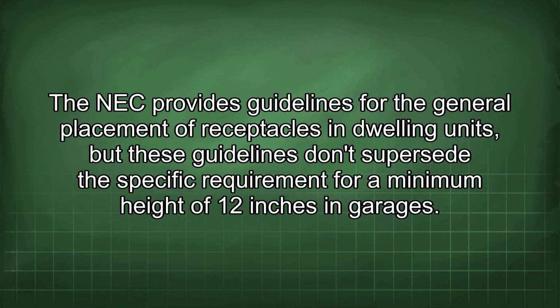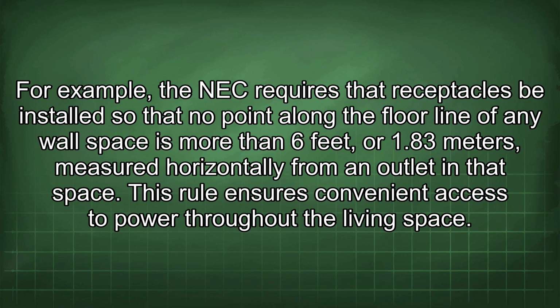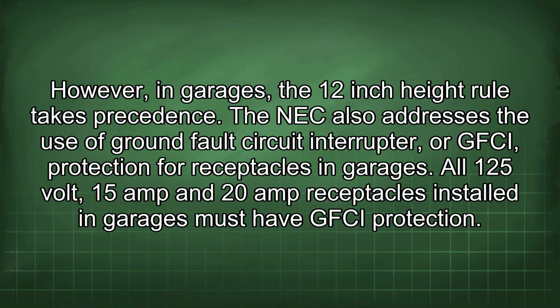The NEC provides guidelines for the general placement of receptacles in dwelling units, but these guidelines don't supersede the specific requirement for a minimum height of 12 inches in garages. For example, the NEC requires that receptacles be installed so that no point along the floor line of any wall space is more than 6 feet, or 1.83 meters, measured horizontally from an outlet in that space. This rule ensures convenient access to power throughout the living space. However, in garages, the 12-inch height rule takes precedence.